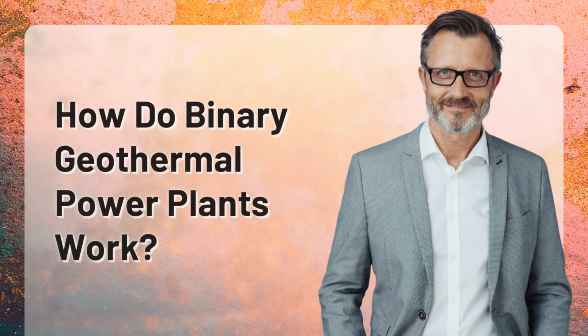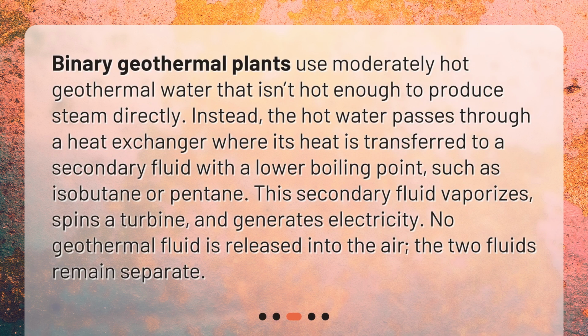How do binary geothermal power plants work? Binary geothermal plants use moderately hot geothermal water that isn't hot enough to produce steam directly. Instead, the hot water passes through a heat exchanger, where its heat is transferred to a secondary fluid with a lower boiling point, such as isobutane or pentane. This secondary fluid vaporizes, spins a turbine, and generates electricity. No geothermal fluid is released into the air. The two fluids remain separate.